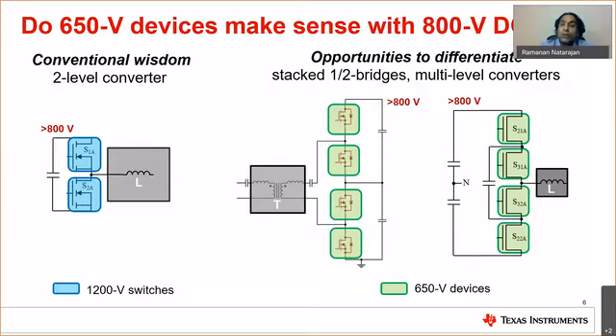Conventional wisdom says the most straightforward way to implement power converters is to choose devices where the voltage capability of the device is higher than the DC link voltage. Looking at the left-hand side, we have the traditional half-bridge two-level power converter, where each switch for, say, an 800-volt DC link application would be rated over 1200 volts. And when the switches are off, they would need to support the entire DC bus voltage. This is a traditional way of thinking.